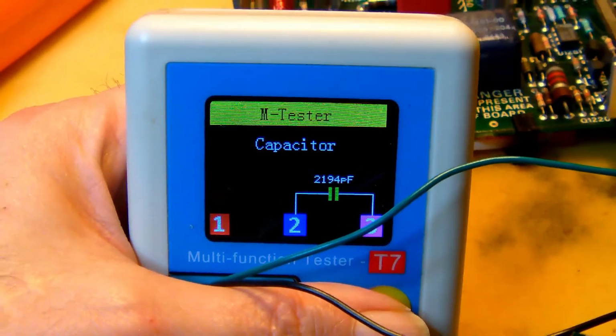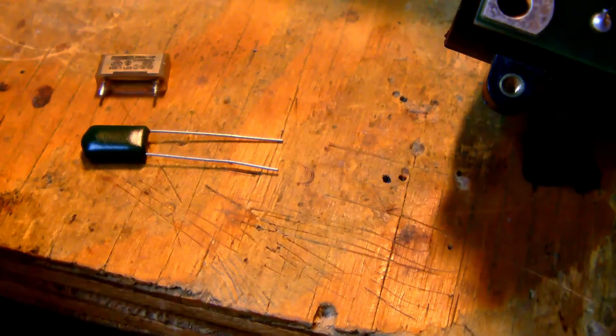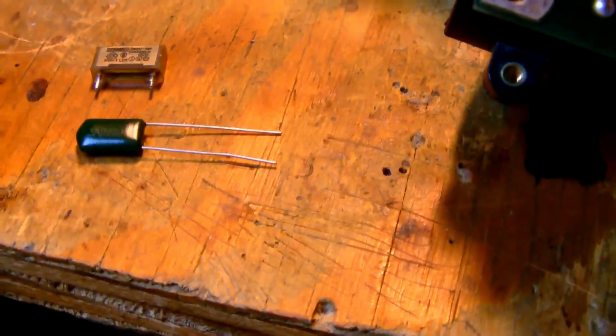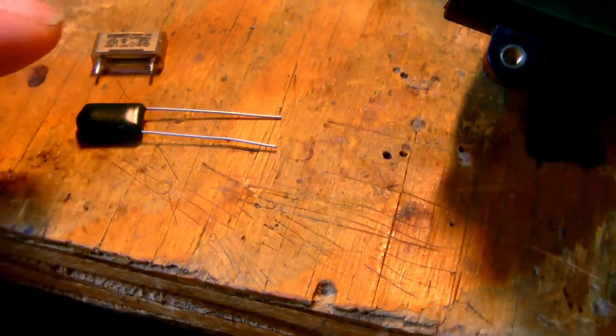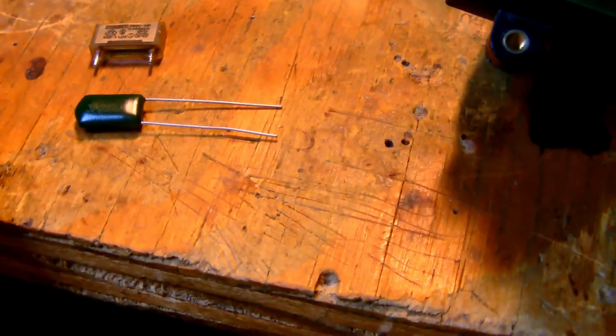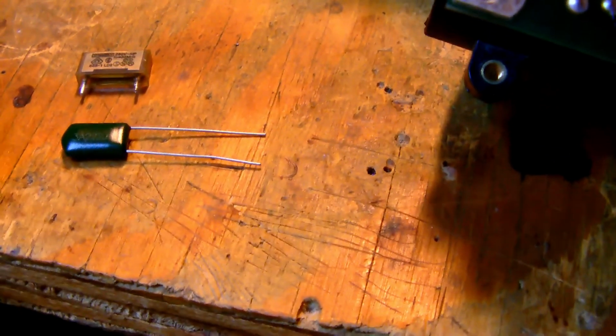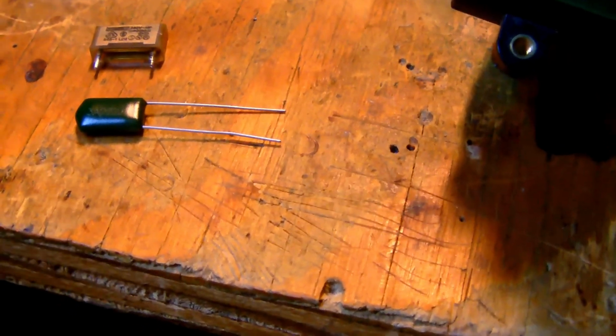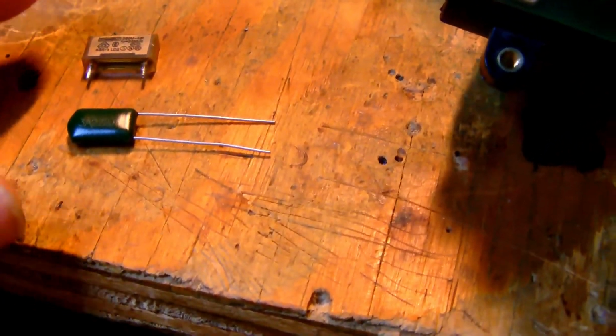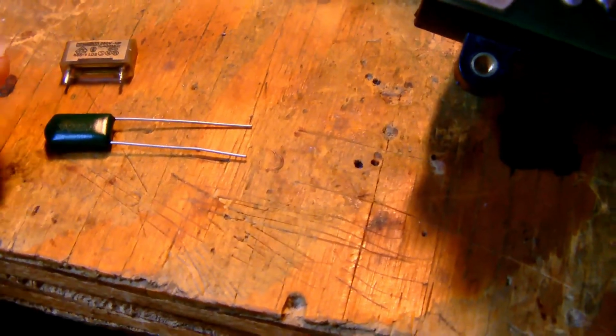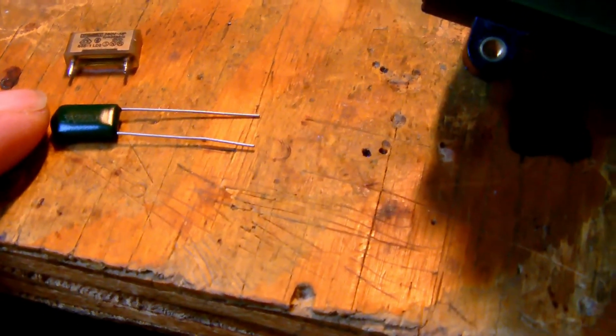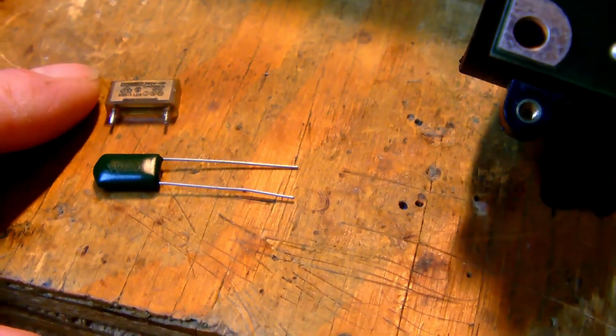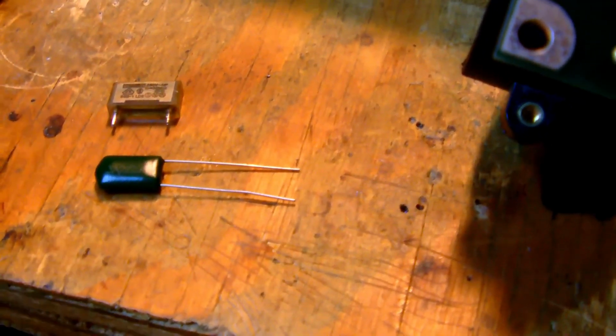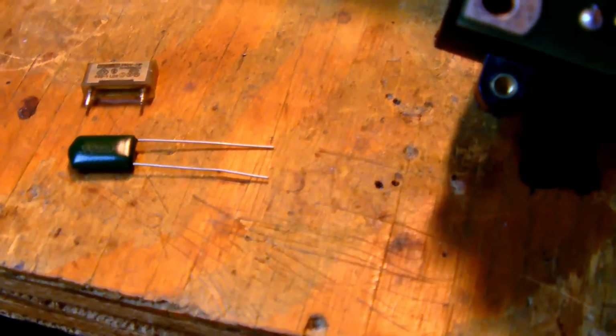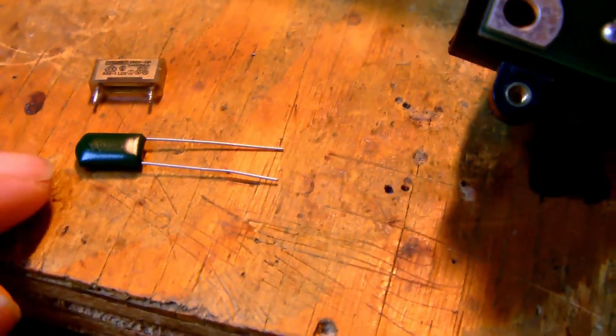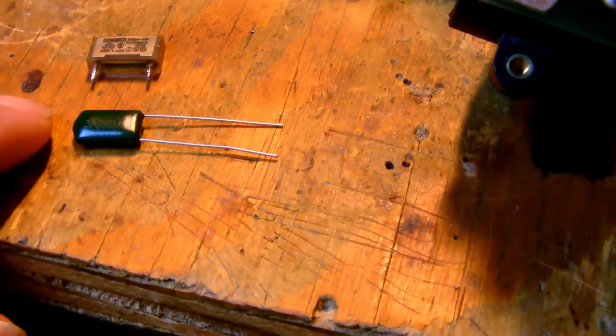(2194 picofarad). While it's certainly recommended to use the exact same value for the replacement capacitor, the voltage rating is slightly different. I would say it's okay to use a higher voltage rated capacitor in lieu of the old capacitor, and that's okay in my opinion. Now, how do I know that this capacitor is rated for 1 kilovolts?